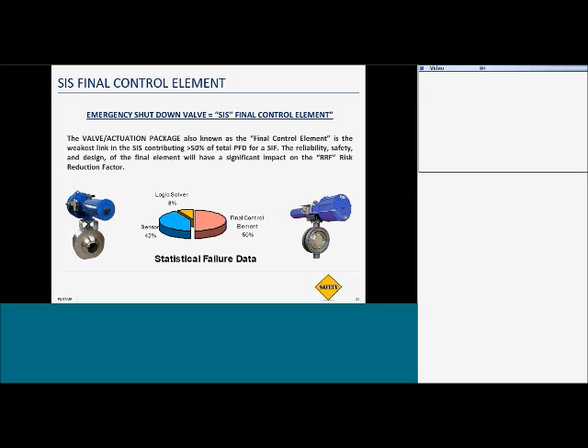If you see that pie in the middle, 42% of the weight of those calculations falls on the sensors, and 8% falls on the logic solver. And this is very conservative, by the way, this analysis. And 50% of the calculations falls on that automated valve package on the final element. Really, this is conservative. It's usually much more than 50% of the weight on the automated valve package. So taking a look at that as an SIS engineer with one of our customers' plants, it's clear to see that the people who can impact safety and optimize the system, and that are potentially the biggest part of our SIS system, is the automated valve package. And there's a few different reasons for this.